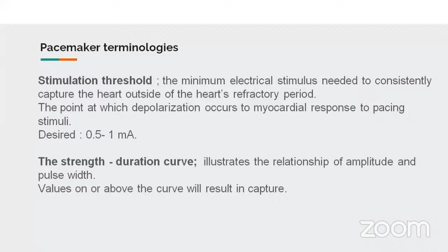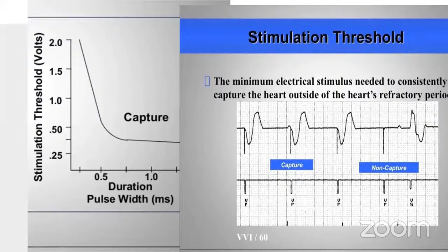The desired level is 0.5 to 1 milliampere. The strength-duration curve illustrates the relationship of amplitude and pulse width. Values on or above the curve are where capture occurs. Capture is the depolarization of the atria or the ventricles in response to the pacing stimulus. Sensing is the ability of the device to detect intrinsic cardiac activity. It should not be undersensed, where there is failure to sense; it should not miss either the P wave or the R wave. Oversensing is being too sensitive to activity, where extracardiac activity is mistaken as intrinsic.